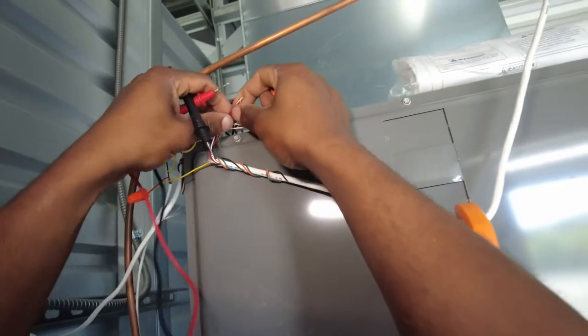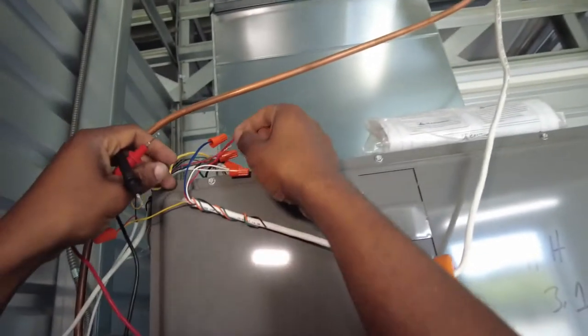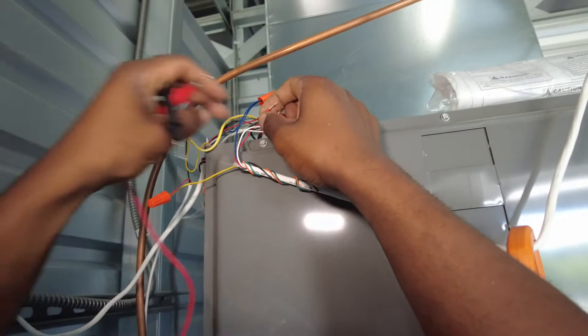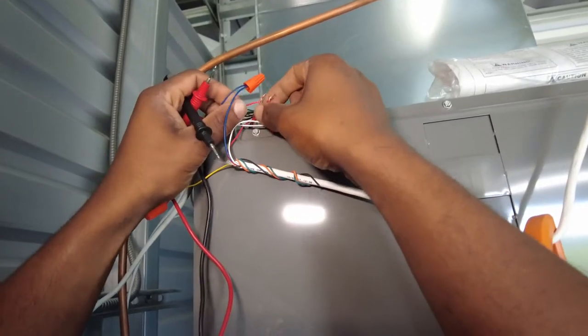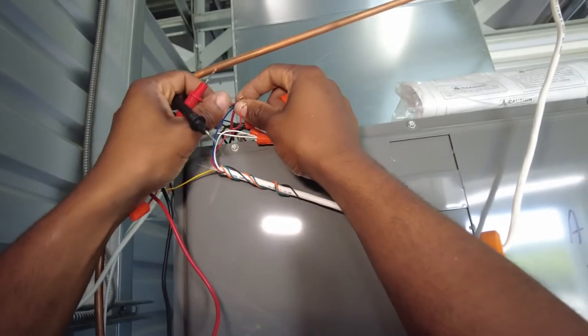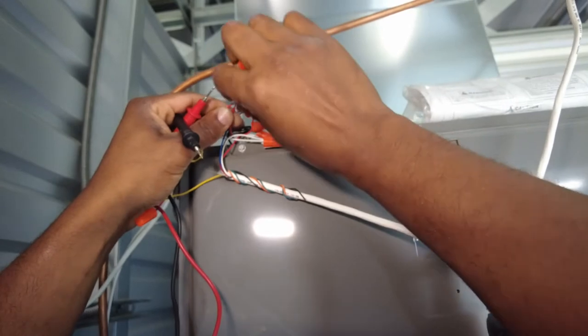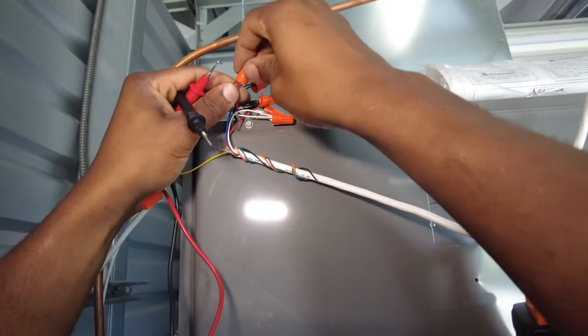Let's see if I take it's coming from the thermostat. Let's take the outdoor unit out of this circuit. Okay, let me just check the outdoor unit. Let's see what that contactor is acting like.